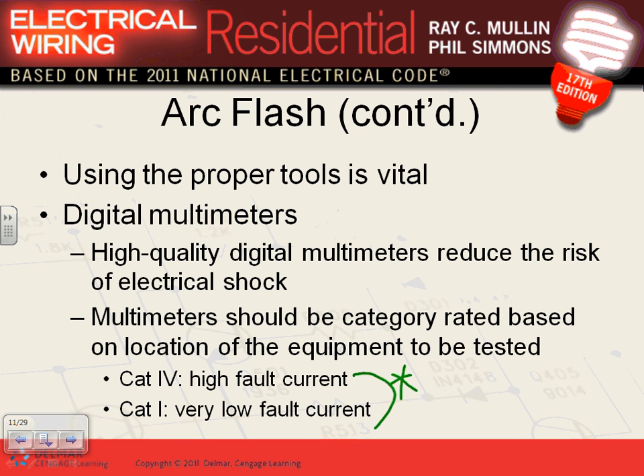So be aware of the meters you have to have, and obviously the high fault current, because if you short with your meter and it's not rated for this short, it could explode in your face, burn your hands, burn your face. So that's always a category for higher fault, one that can handle higher fault instead of the lower fault meters.